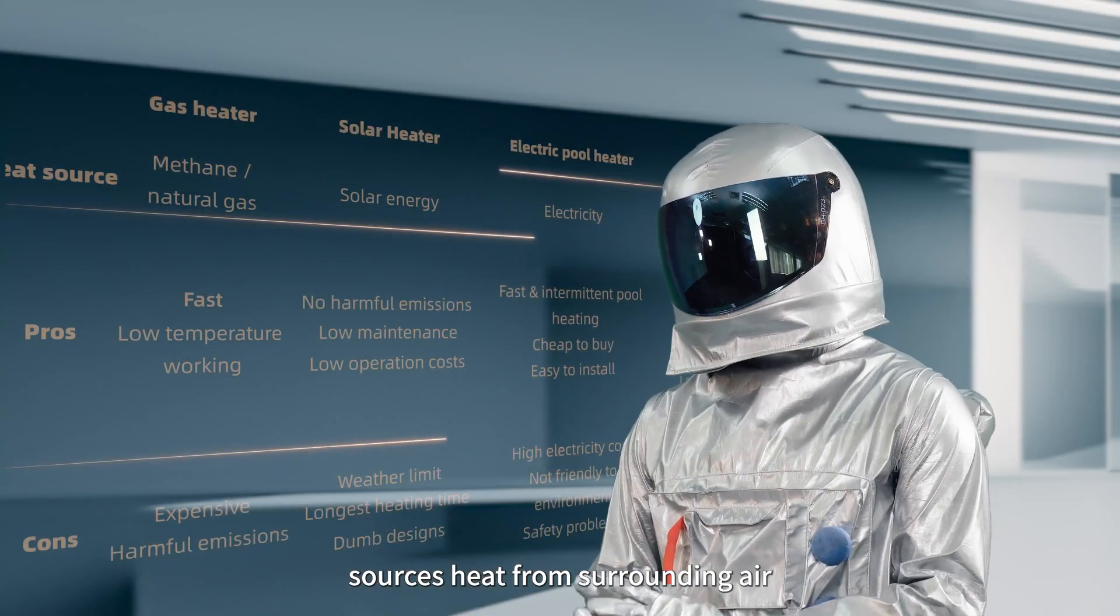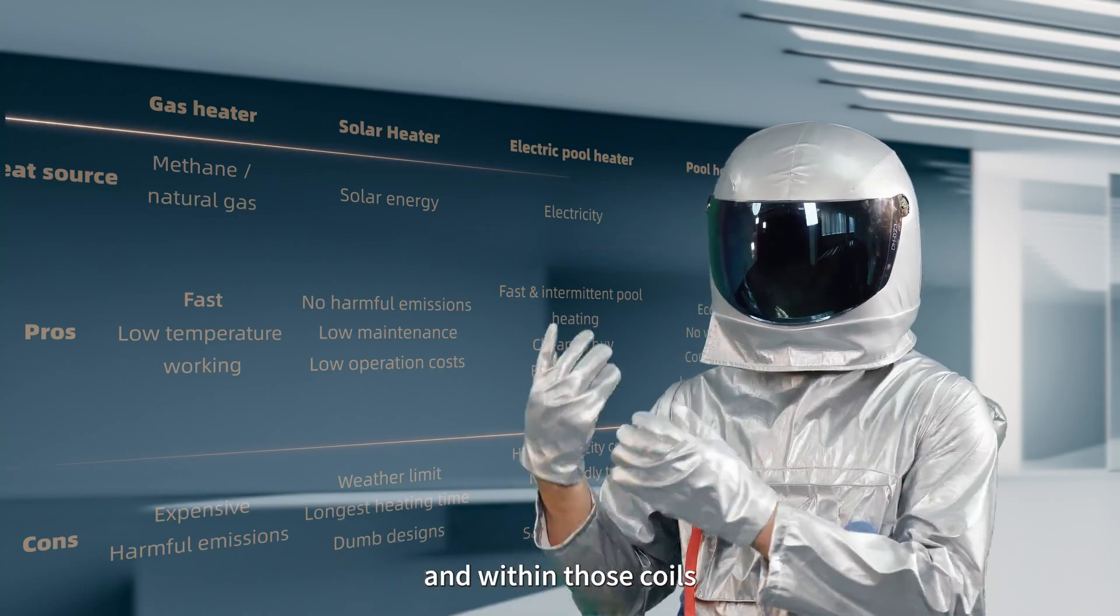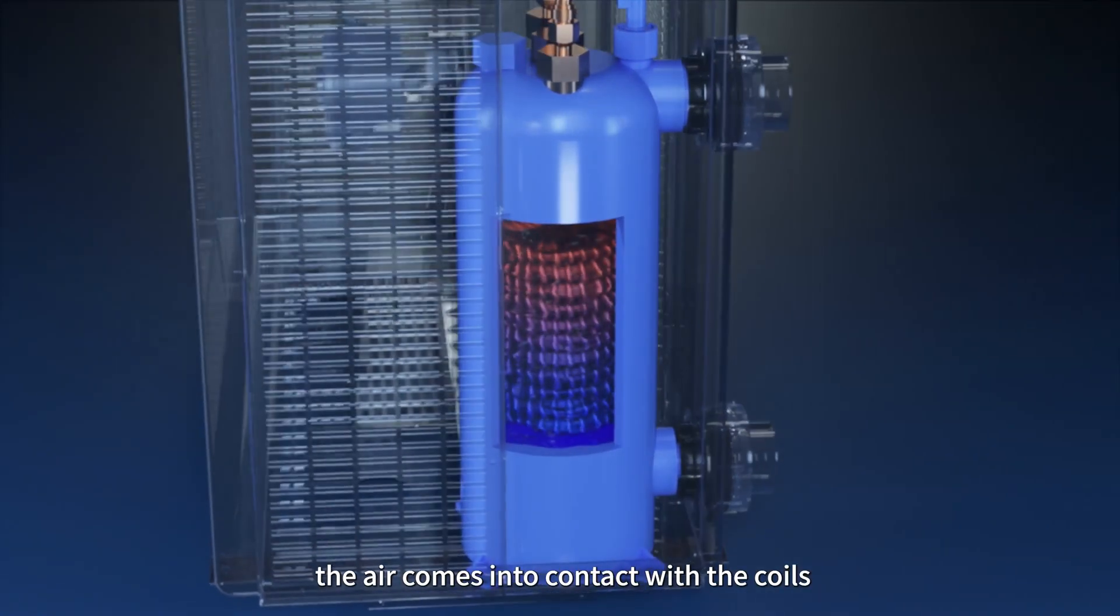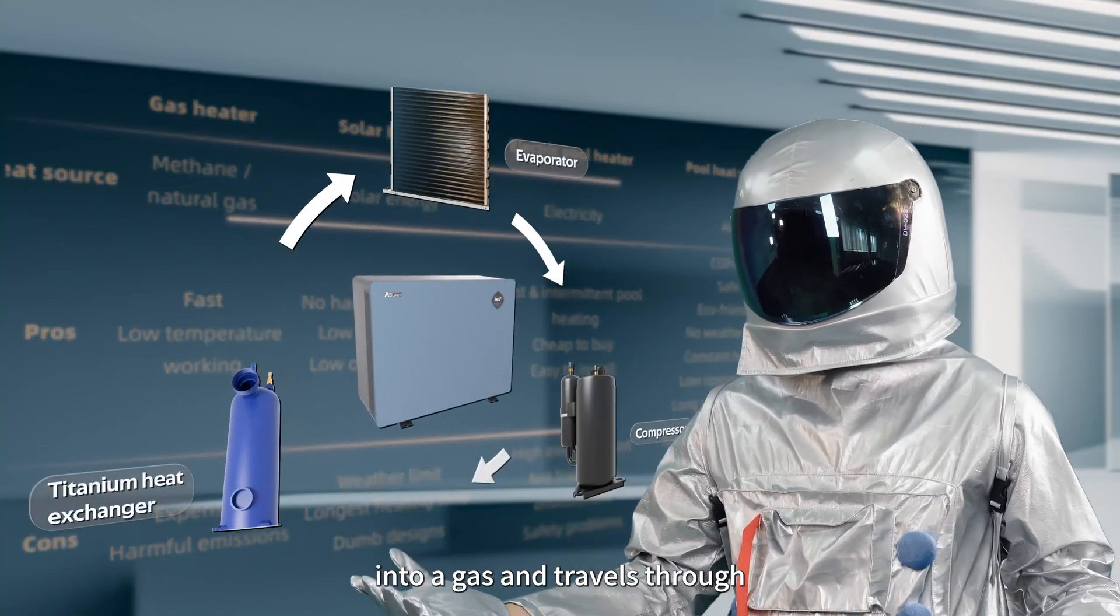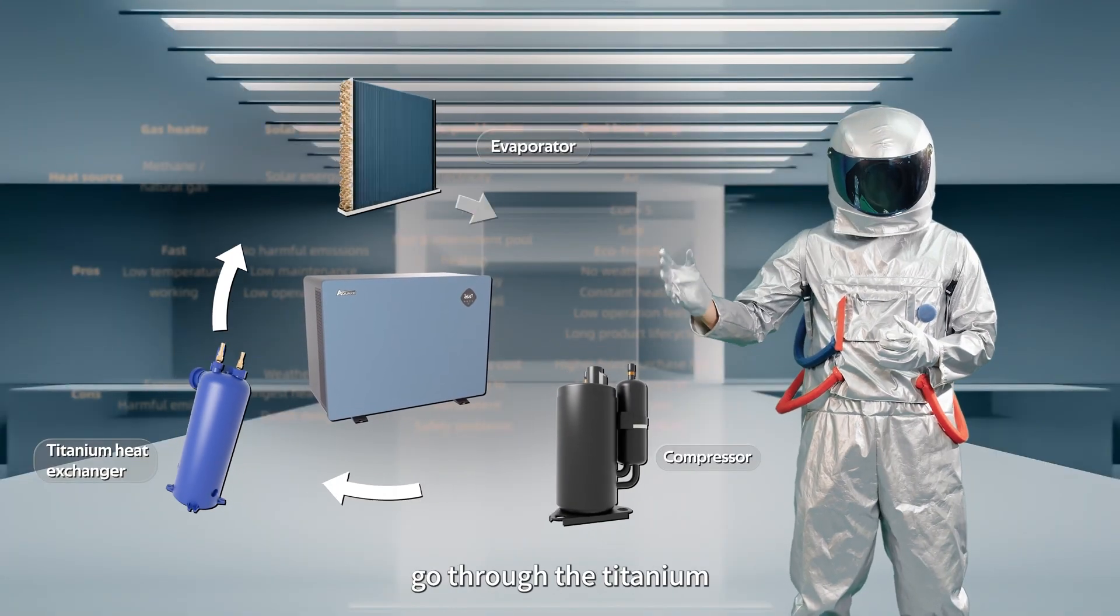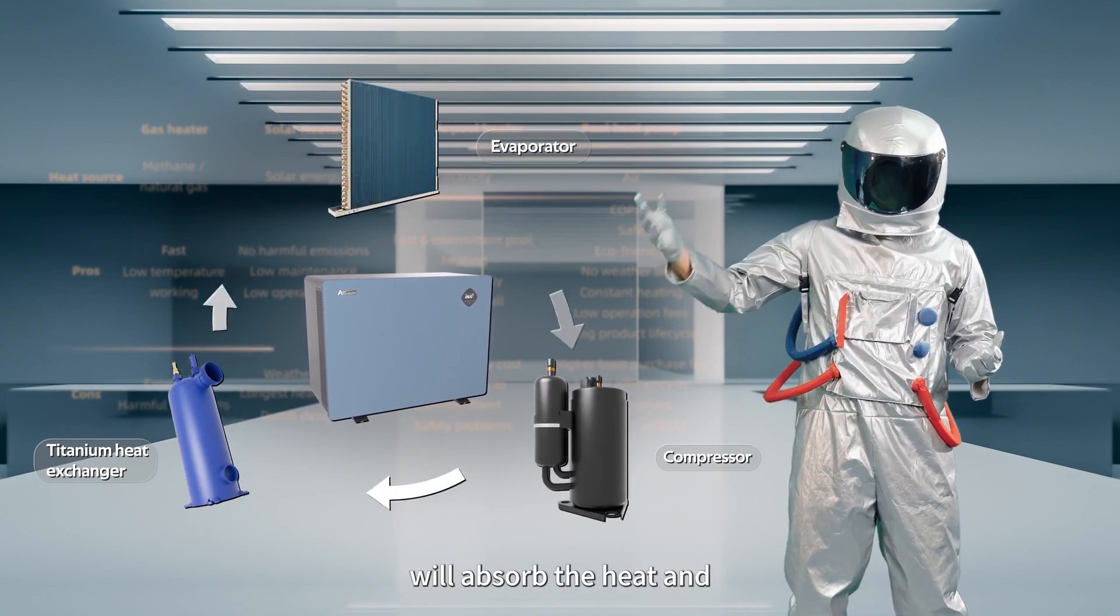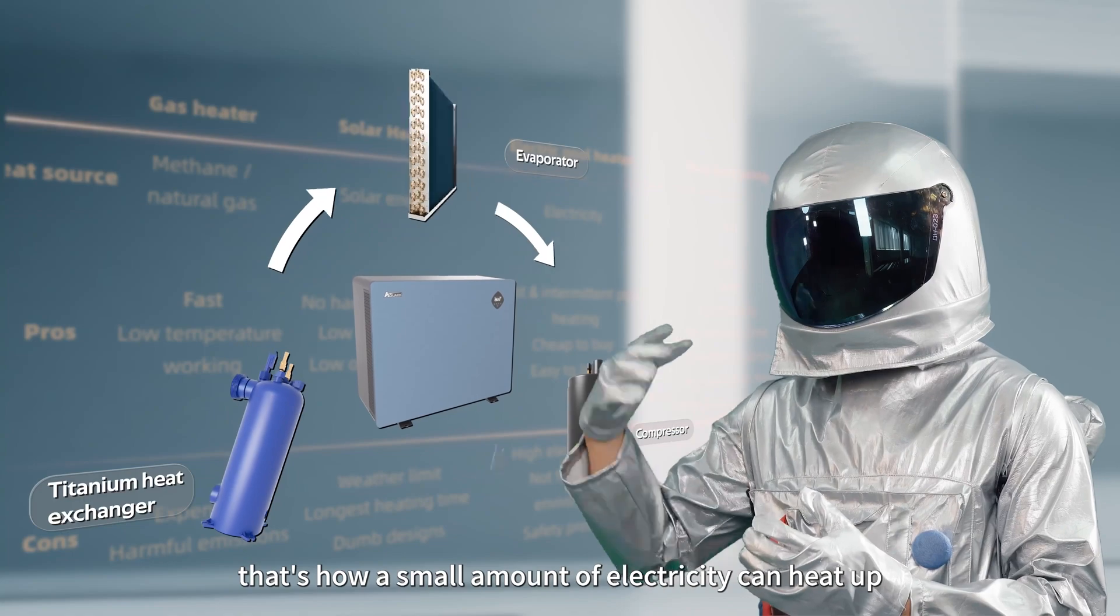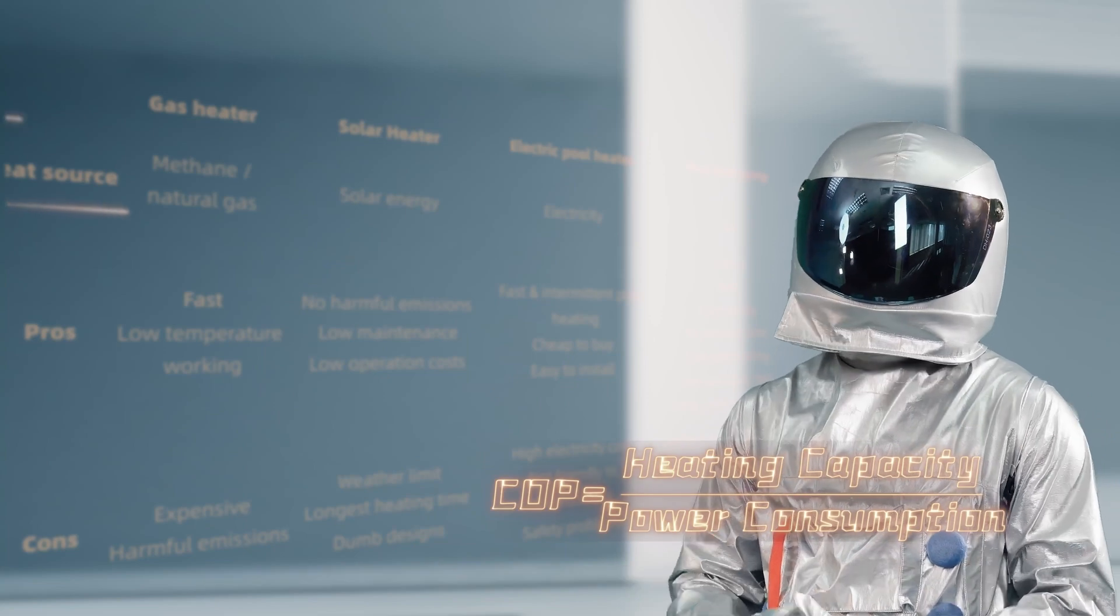Pool heat pump sources heat from surrounding air and transfers it to the water. Inside the heat pump are copper coils and within those coils is the refrigerant R32. When heat that is pulled from the air comes into contact with the coils, the liquid refrigerant turns into gas and travels through a compressor to become high pressure, high temperature gas. The gas refrigerant goes through the titanium heat exchanger inside. Pool water around the copper coils will absorb the heat and its temperature therefore increases. You see, that's how a small amount of electricity can heat up a pool, and that's why pool heat pumps have a relatively high COP of around 5.